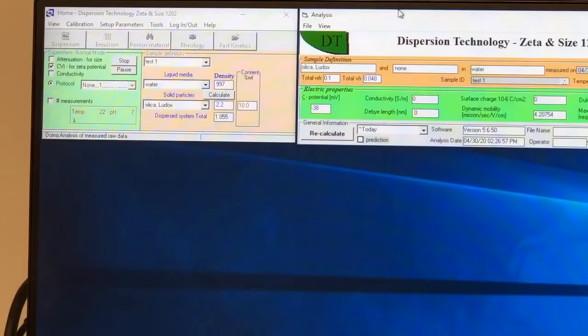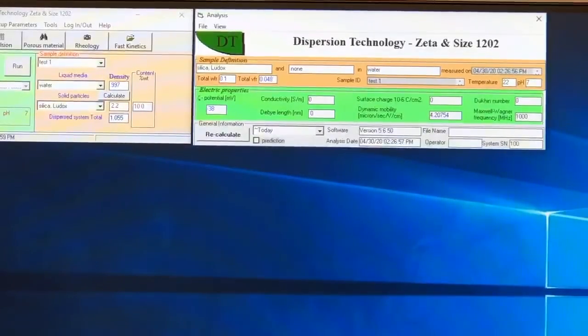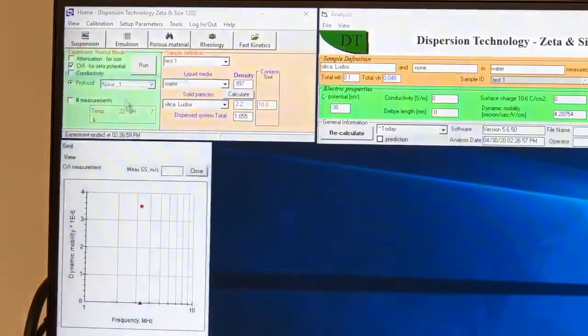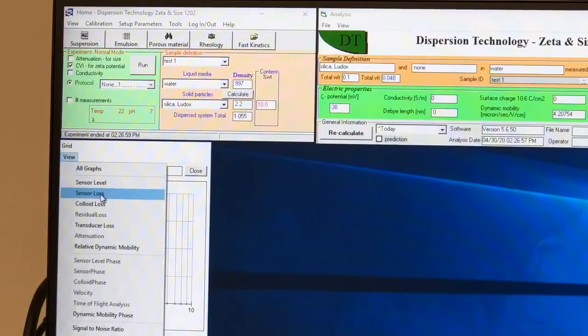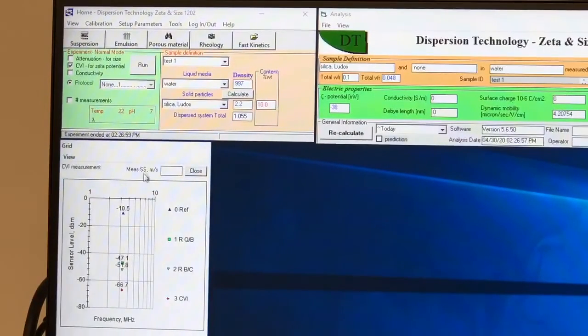Part 3. Verification. There is a form that allows for verification that the probe is functioning properly by displaying the signal level at different junctions inside of the probe. This form can be reached from the home screen by selecting View, Grid Raw Data. This will bring up the Grid Raw Data window. On this form, we select View Sensor Level. You can find a snapshot of this form with proper values for different junctions in the manual.